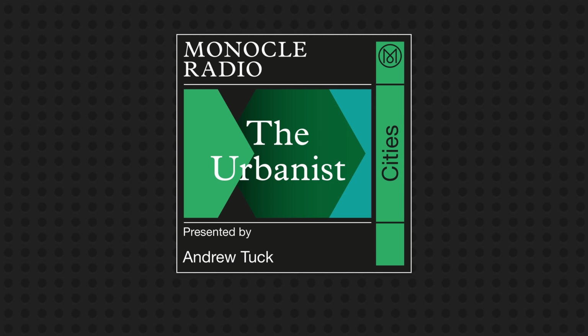Christoph, thank you for joining me. Can we start by just outlining the scale of this project that you've recently completed? The British Library really is the biggest project that we've ever done, and it's actually the biggest project that's ever happened for solar thermal in the United Kingdom. It's quite unique in its application. We have installed nearly 400 kilowatts of solar thermal and PVT, which is hybrid solar thermal and PV, a unique product that we've developed.